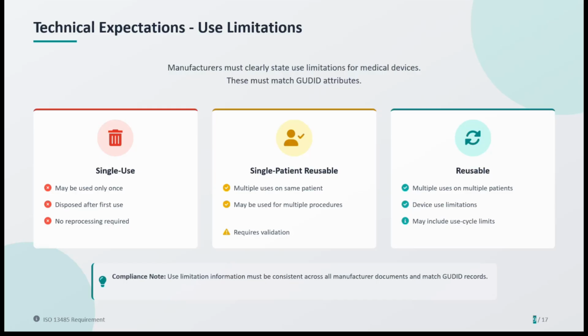And then, of course, we know our reusable devices are instruments, screws, and plates. They may be used on multiple patients with validated reprocessing between uses. For reusable devices, validation includes the full cycle: handling and use, point of care use and cleaning, decontamination, assembly, sterilization, and packaging. If the label, IFU, and GUDID entry don't match on these points, that's a red flag that has to be resolved.